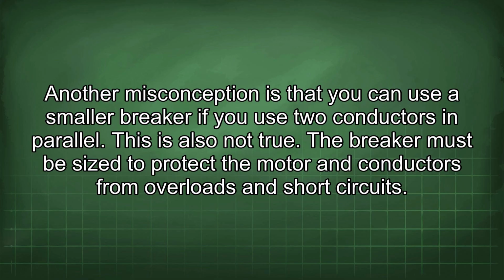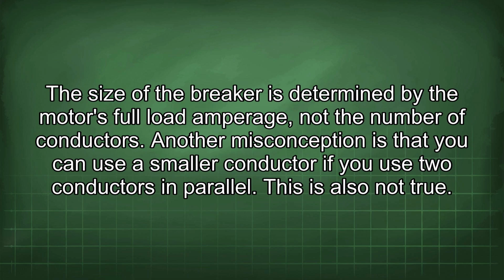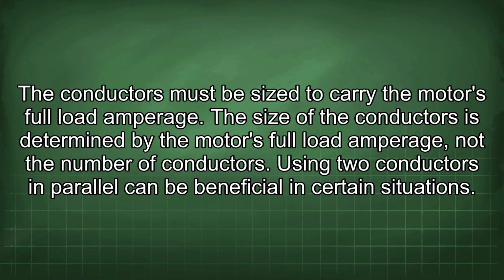The breaker must be sized to protect the motor and conductors from overloads and short circuits. The size of the breaker is determined by the motor's full load amperage, not the number of conductors. Another misconception is that you can use a smaller conductor if you use two conductors in parallel. This is also not true. The conductors must be sized to carry the motor's full load amperage. The size of the conductors is determined by the motor's full load amperage, not the number of conductors.